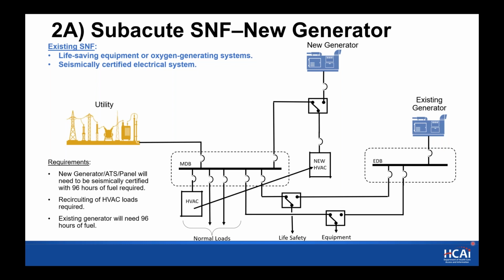So the distinction is between these two. If the subacute does have existing life-saving and oxygen generator, you would have to go back and either transfer those loads to the new panel or address the 96 hours at the existing generator. Next slide, please.